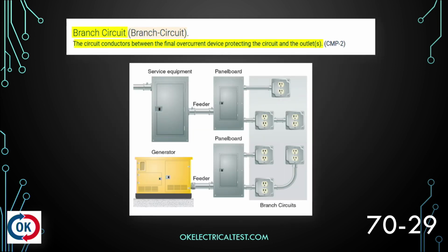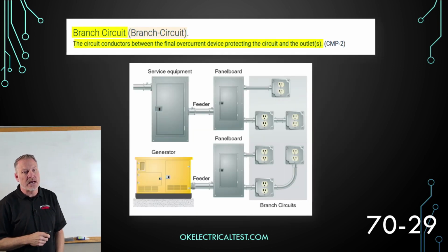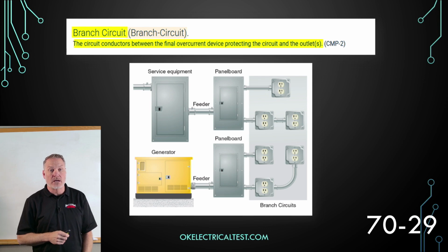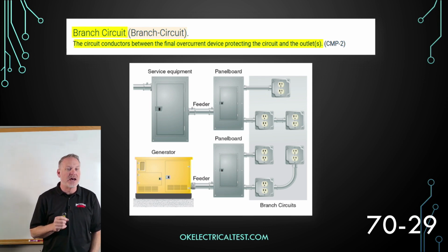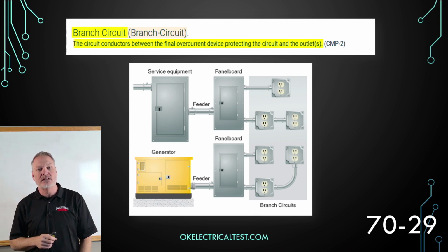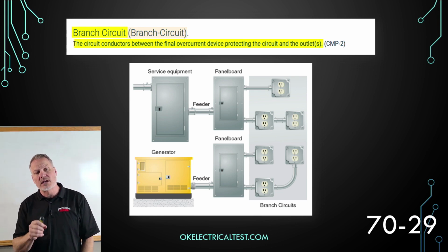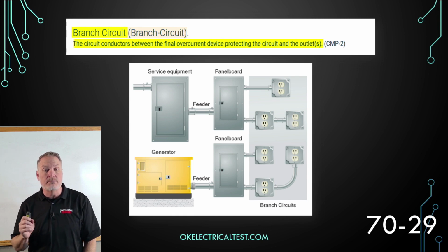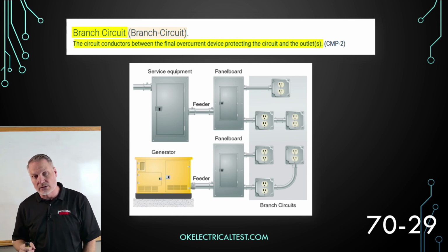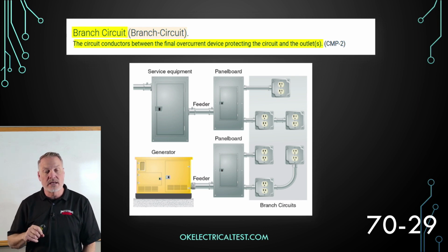Let's go to branch circuit. Still on page 29, branch circuit, or branch dash circuit. That's really nuanced, right? The circuit conductors between the final overcurrent device protecting the circuit and the outlets. So you'll see here on our illustration, our branch circuit is going to go from that panel board to the outlet, okay? So that indication there, you may call that something different in the field.